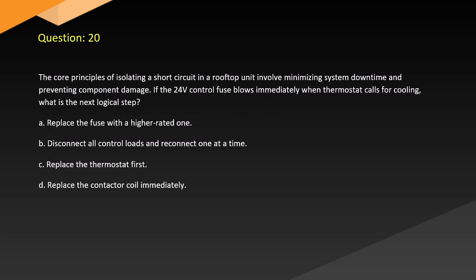Question 20. The core principles of isolating a short circuit in a rooftop unit involve minimizing system downtime and preventing component damage. If the 24-volt control fuse blows immediately when the thermostat calls for cooling, what is the next logical step? A. Replace the fuse with a higher-rated one. B. Disconnect all control loads and reconnect one at a time. C. Replace the thermostat first. D. Replace the contactor coil immediately.